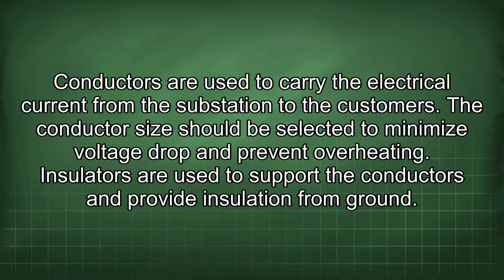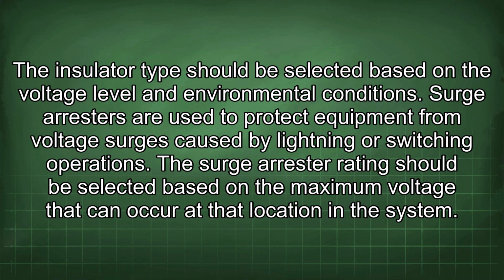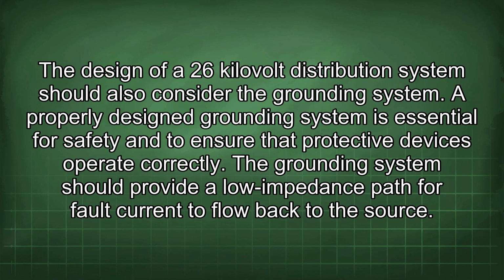Conductors are used to carry the electrical current from the substation to the customers. The conductor size should be selected to minimize voltage drop and prevent overheating. Insulators are used to support the conductors and provide insulation from ground. The insulator type should be selected based on the voltage level and environmental conditions. Surge arresters are used to protect equipment from voltage surges caused by lightning or switching operations. The surge arrester rating should be selected based on the maximum voltage that can occur at that location in the system. The design of a 26 kilovolt distribution system should also consider the grounding system.